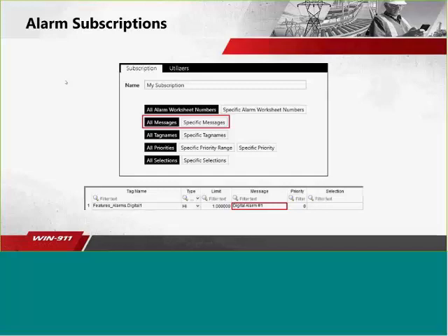In this example, if I wanted to pull in this alarm that is in the screenshot at the bottom, if I chose specific messages and typed in the word digital, any alarm that goes active that has the word digital in the message would match this subscription and would come into Win911. You can also do this with tag names. Same kind of deal with a string wildcard. We can also do priority.